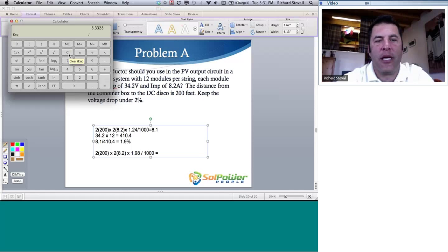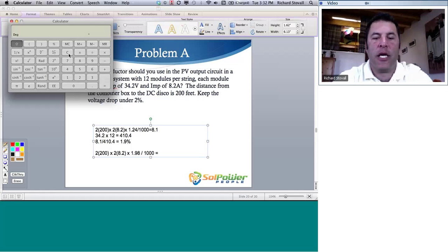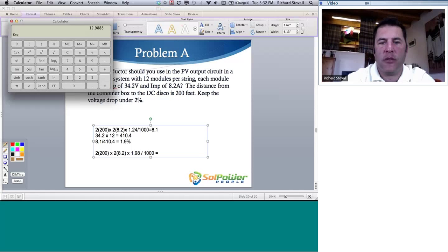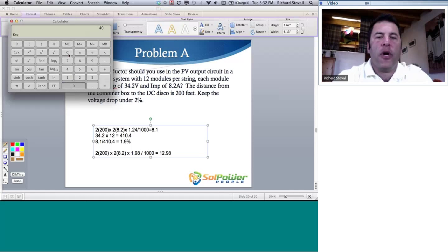Okay. So I'll go 400 times 16.4 times 1.98 divided by 1,000, divided by 410.4, is 3.16%. So I'll take it a step back. 400 times 16.4 times 1.98 divided by 1,000 is equal to 12.98. I'm going to run through that one more time. 400 times 16.4 times 1.98 divided by 1,000 is equal to 12.98. Okay, so that's correct.